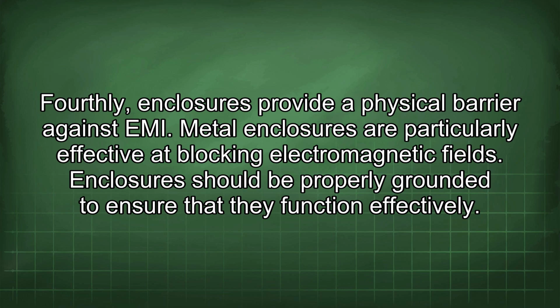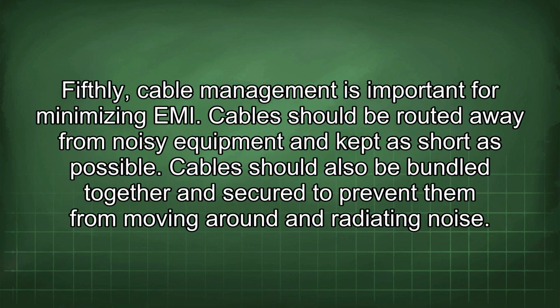Metal enclosures are particularly effective at blocking electromagnetic fields. Enclosures should be properly grounded to ensure that they function effectively. Fifthly, cable management is important for minimizing EMI. Cables should be routed away from noisy equipment and kept as short as possible. Cables should also be bundled together and secured to prevent them from moving around and radiating noise.